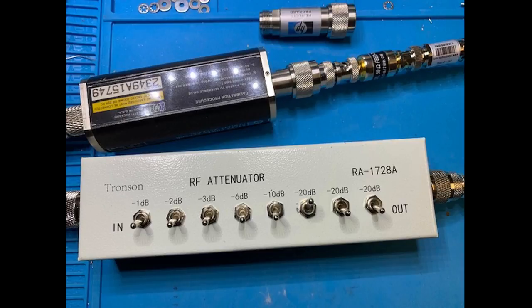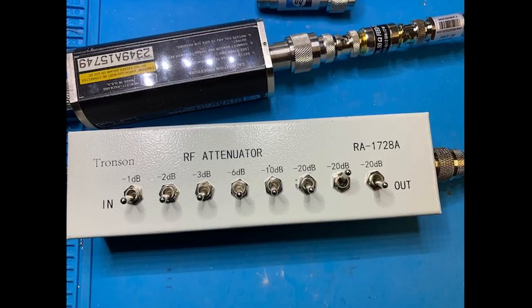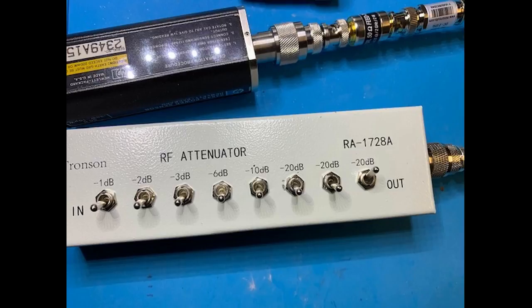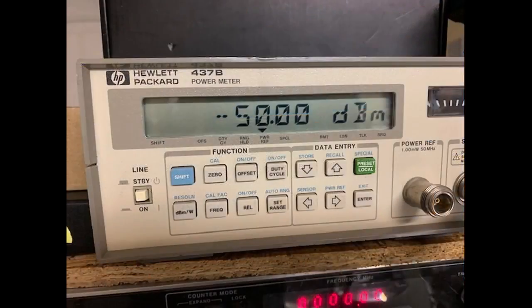Switching the 20 dB attenuator switch to on, the power meter reads minus 50 dBm. As the various attenuator switches are selected, this test confirms a better than plus or minus 0.02 dB precision.